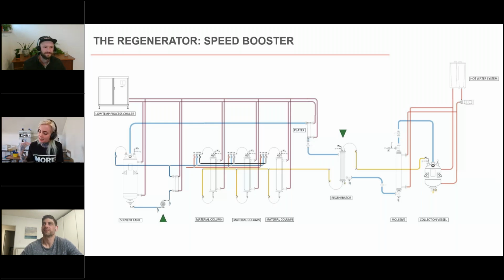If you ever accidentally aspirate any oil or anything, if you're using molecular sieve beads, that dust can go into the coils. Coils are not the best solution for the type of heat exchanger we need, and that plate exchanger will eliminate all of those problems.